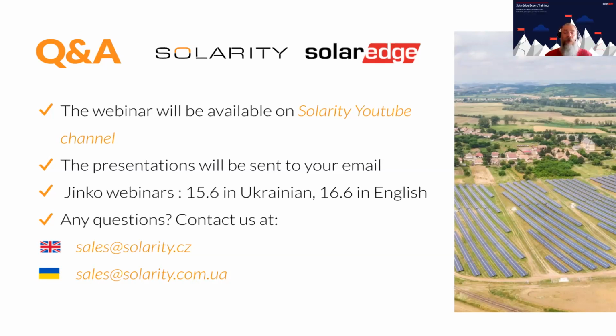Yes, so if you just want to export to the grid, the meter serves a purpose by showing you what you're exporting to the grid. It shows you what you're consuming, things like that. And the meter is a great tool for later saying, oh, I actually want to add a battery. What size battery do I need? Or what smart energy devices could I use? But if your sole purpose is just to export to the grid, then no, you do not need to install the meter.